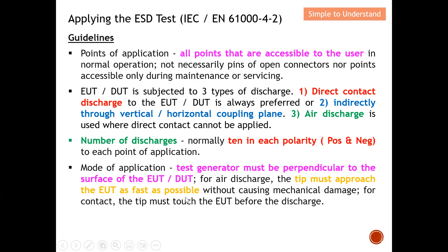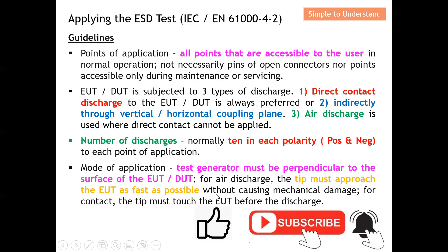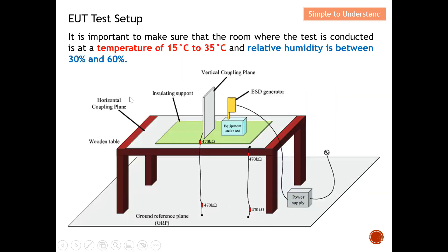For air discharge, the tip must approach the EUT as fast as possible — you cannot take your time approaching, as the discharge may occur prematurely. You need to move as fast as possible toward the EUT without causing mechanical damage. For contact discharge, the tip must touch the EUT before you execute the discharge. If you find this helpful, please like this video and subscribe to this channel.